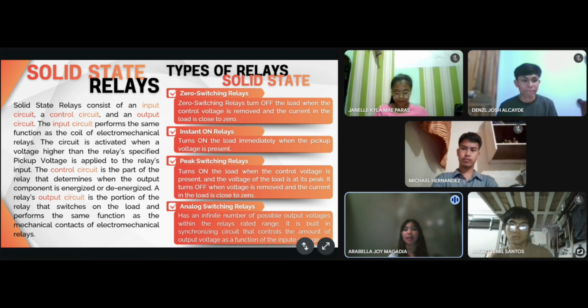Now there are different types of solid state relays and here are the four main ones. First is the zero switching relays. Ito yung type na nagto-turn off ng load kapag tinanggal na yung control voltage at yung current sa load ay malapit na sa zero. The advantage of this is smoother switching and less electrical noise. Second is instant on relays. Very straightforward. Kapag present na yung pickup voltage, agad-agad siyang nagto-turn on. Walang delay, so perfect sa mga applications na kailangan ng mabilisang response.